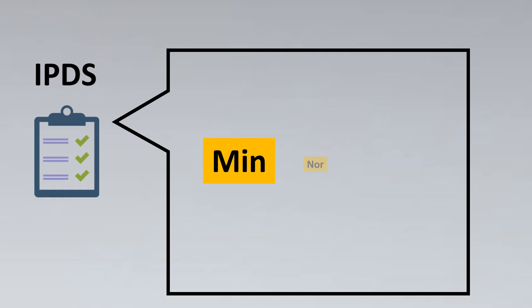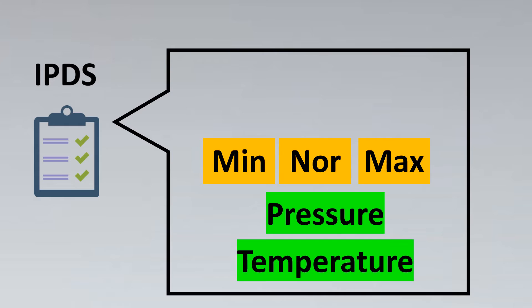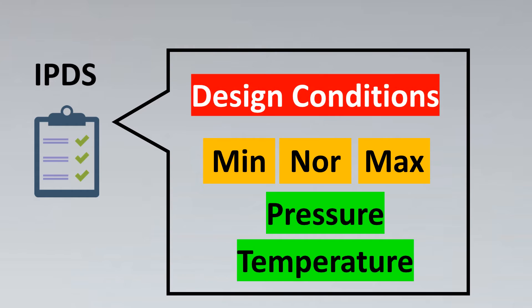The IPDS will also have the minimum, normal, and maximum conditions of pressure and temperature that the particular instrument will have to face. You would also have to get the design conditions — for example, the design pressure and temperature. The design conditions are something which the instrument would experience at very low or extreme intervals, maybe during plant startup, but won't be regularly exposed to.